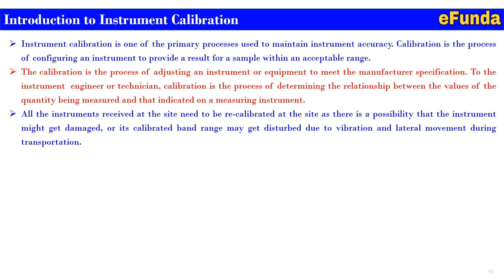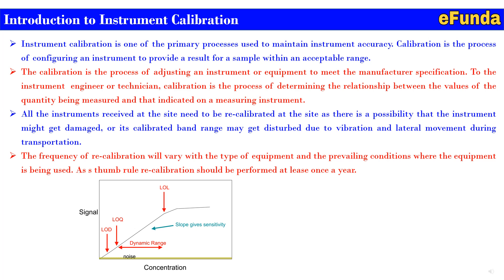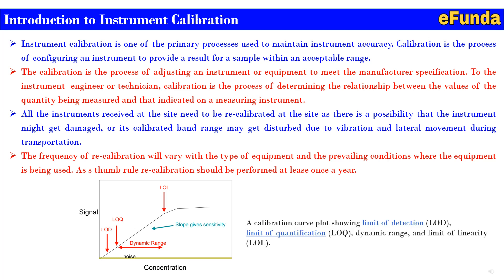The frequency of recalibration will vary with the type of equipment and the prevailing conditions where it is used. As a thumb rule, recalibration should be performed at least once a year, and may vary based on the application and client requirements. One can see the relationship where signal and concentration are plotted on a graph, showing LOD (limit of detection), LOQ (limit of quantification), dynamic range, noise, slope (sensitivity), and LOL (limit of linearity) — forming the calibration curve.